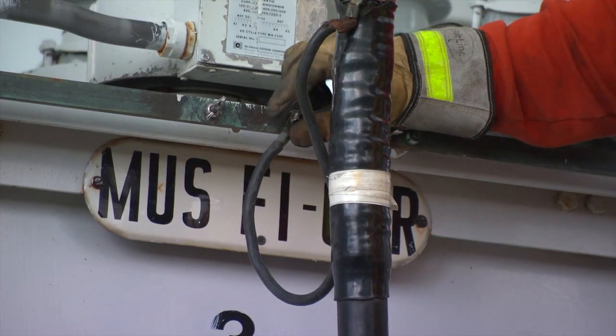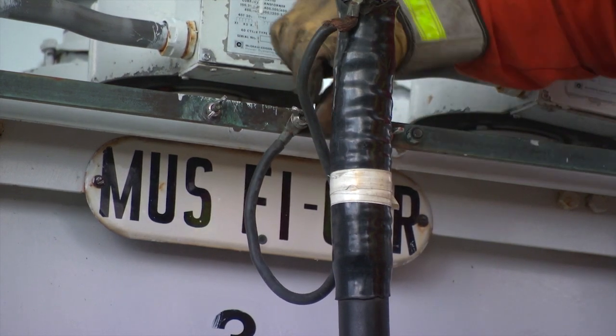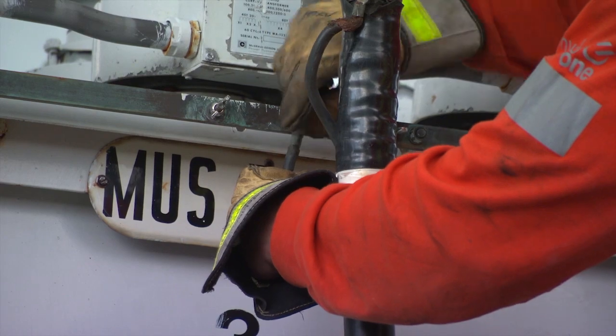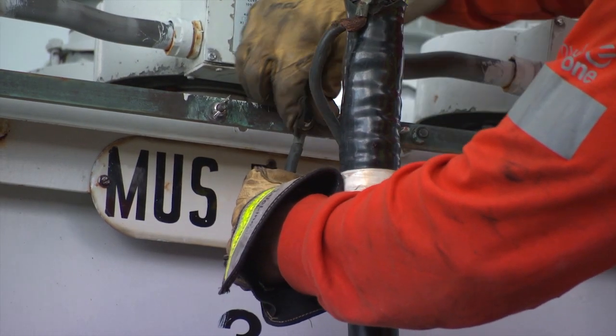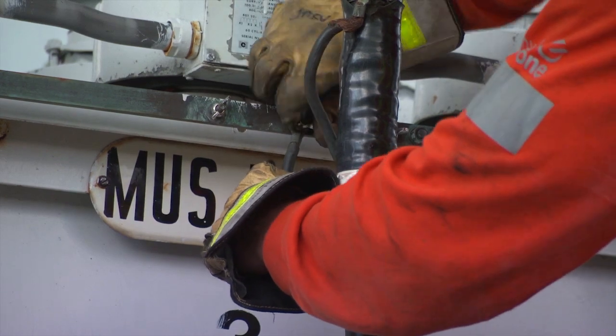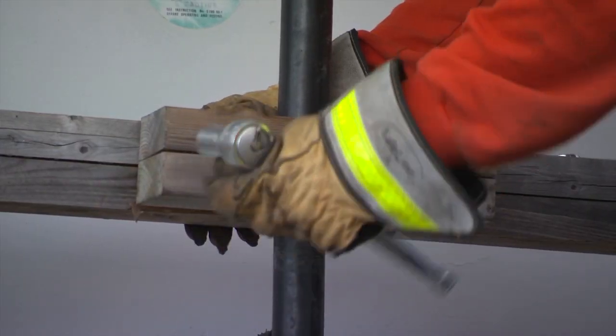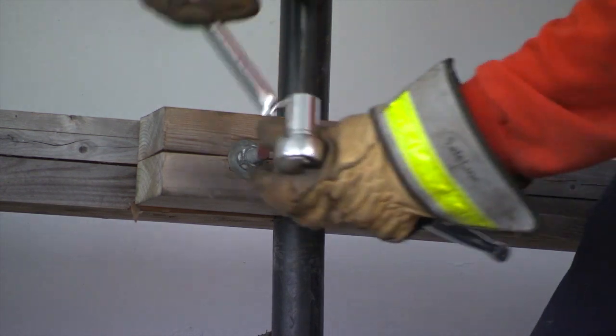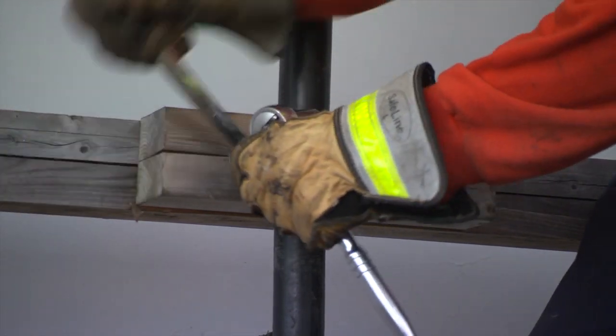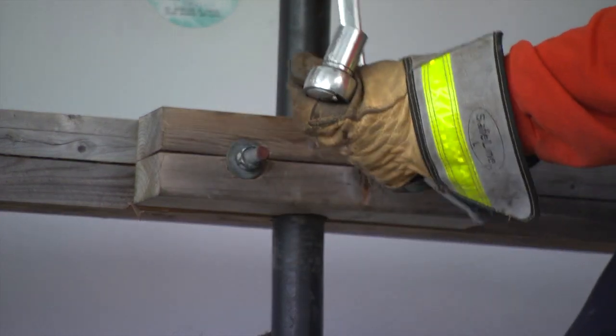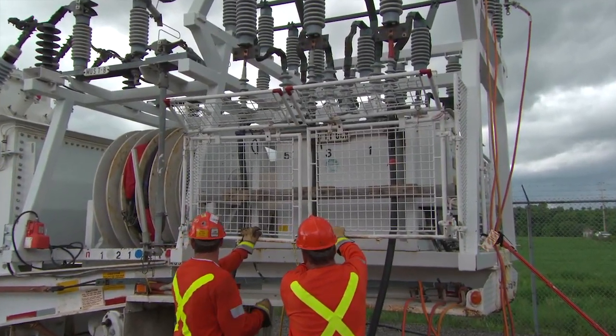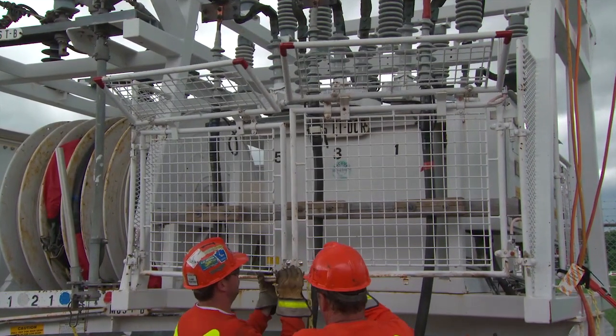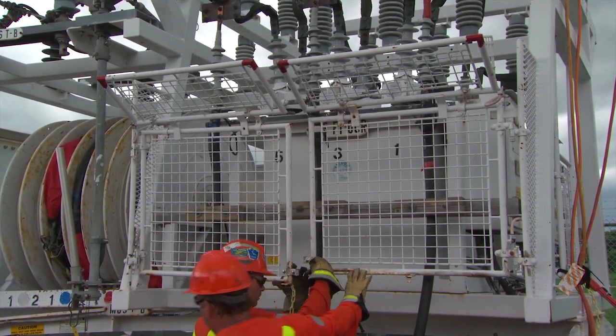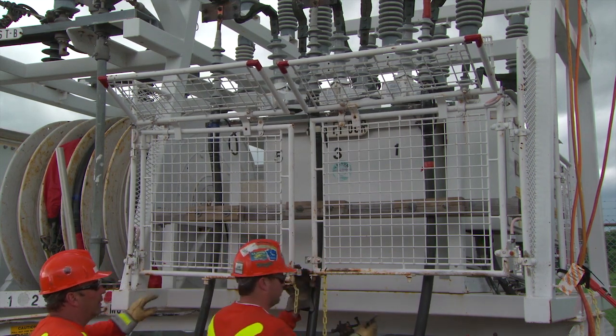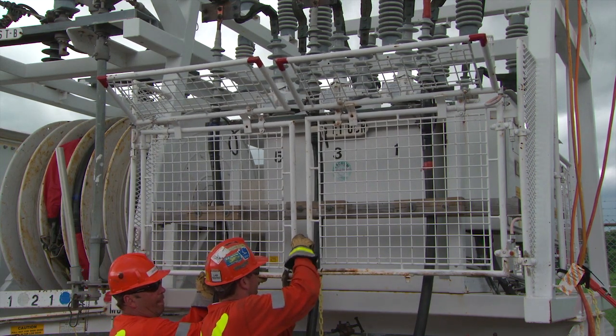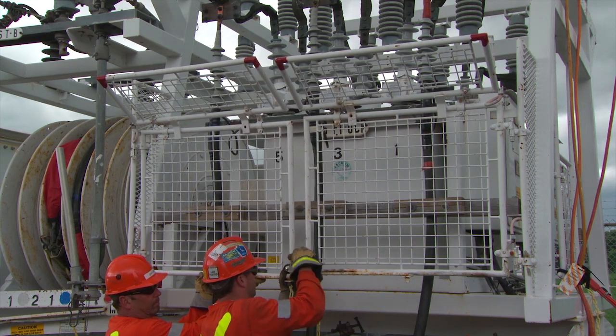Once all cable connections have been checked secure, connect each cable concentric neutral to the MUS ground bar, located near the top of the reclosers. Reinstall the cable support blocks, allowing for some movement due to thermal expansion. Ensure that electrical clearances are maintained and the cables are not pinched, squeezed, or damaged by the wooden blocks. Close and secure the MUS recloser gates with the upper barrier secured in the outermost position. This is required to maintain electrical clearances when the load recloser bushings become energized.